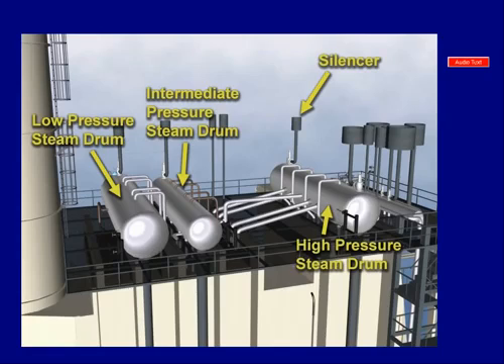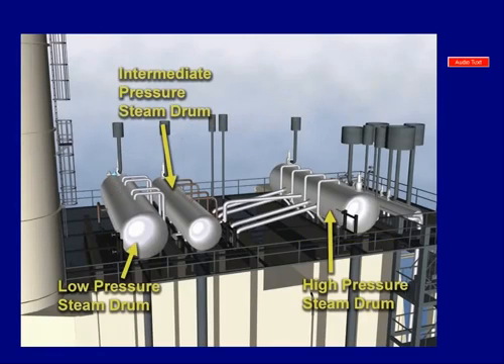One HRSG is provided for each of the two gas turbines, and two HRSGs provide steam for the single steam turbine. This is called a two-on-one combined cycle plant configuration. Both of the HRSGs operate at three pressure and temperature levels with natural circulation.